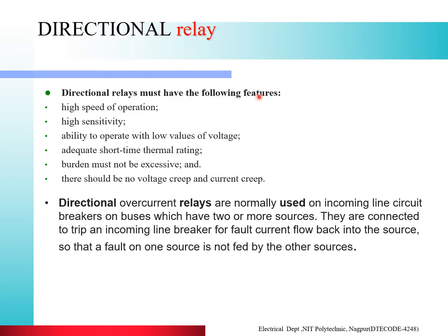The directional relay must have the following features: high speed of operation, high sensitivity, ability to operate with low values of voltage, adequate short time thermal rating, burden must not be excessive, and there should be no voltage creep and current creep.